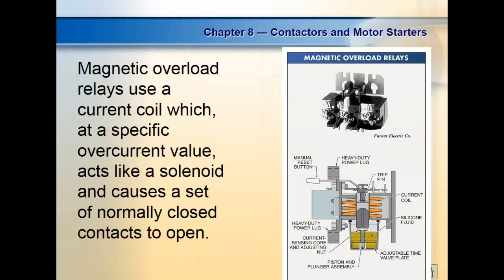It's a DC solenoid. So how can we tell if a solenoid or a relay is AC or DC? If you got a 120 volt AC coil and you put it on 120 volts DC, you're going to burn it up and blow fuses. In AC, the opposition on a coil is given by this formula, 2 pi FL. Y'all don't need to know this, but 2 pi is a given, so normally we just use 6.28. The frequency is what you apply to it, so Alabama Power would be 60 hertz. And L is basically how many loops you have in a coil, called the inductance.